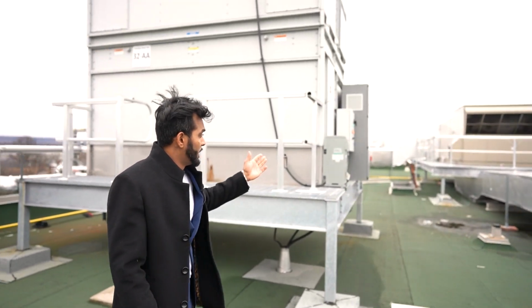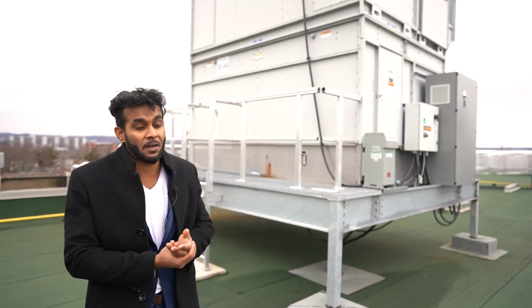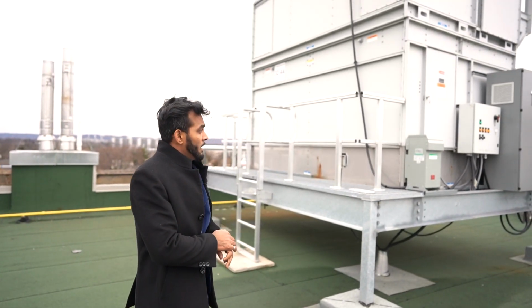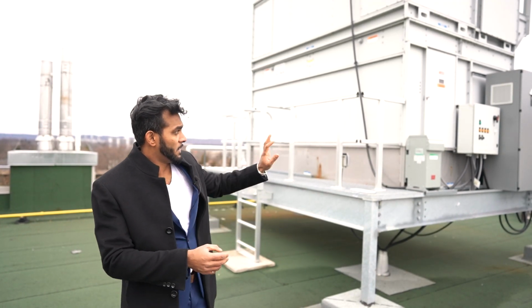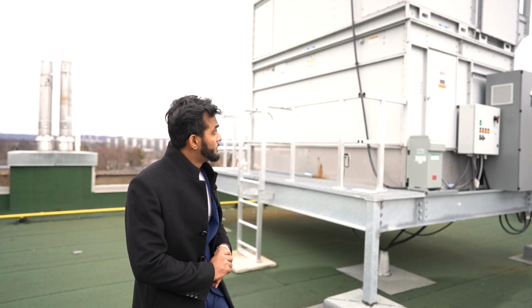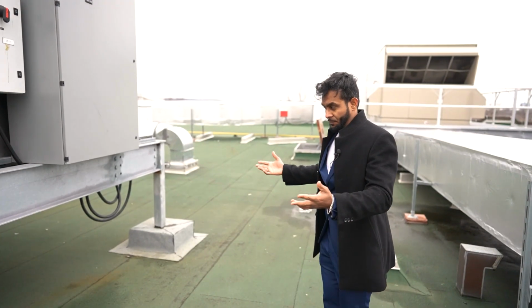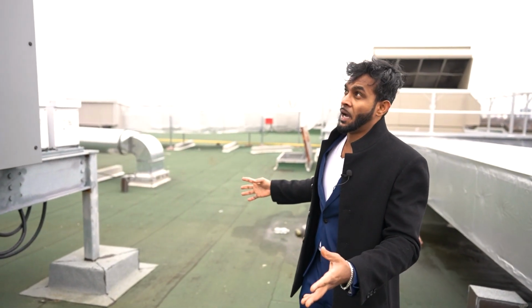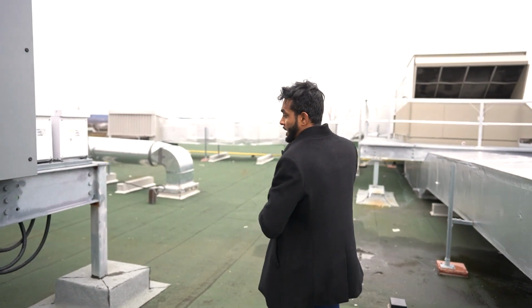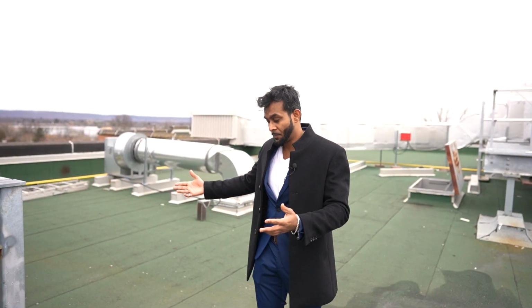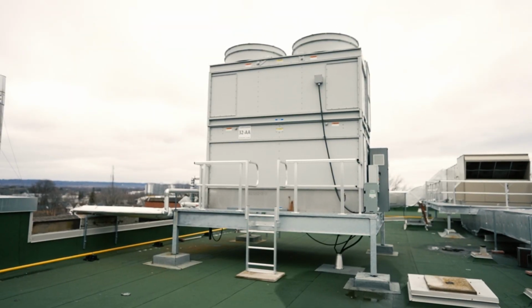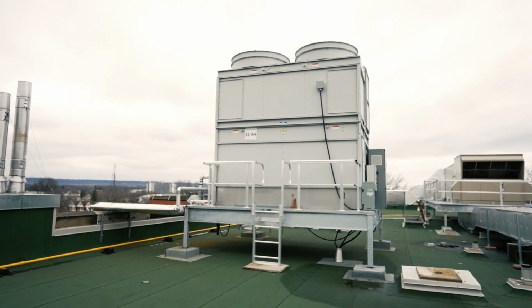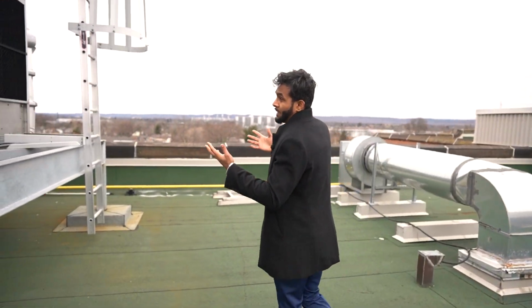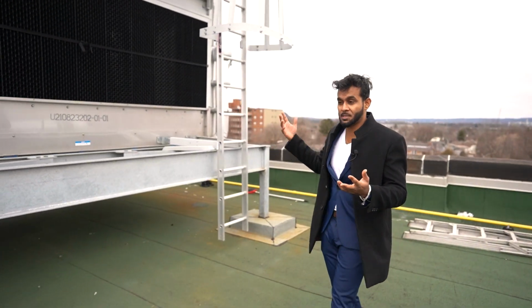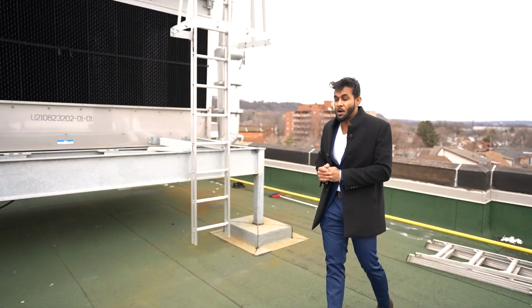On this side, we have the controls and the high voltage. This runs on a 600 volt 3-phase, so we had to get electricians to make sure that it was done right. And the structure was done by our GC. This is a brand new structure that was introduced to house the cooling tower. What they had to do was reinforce the entire structure all the way to the basement, in the boiler room, to carry this weight on top of the roof. Especially with so much water running through the system, you have to make sure that it's structurally sound to put on the roof.